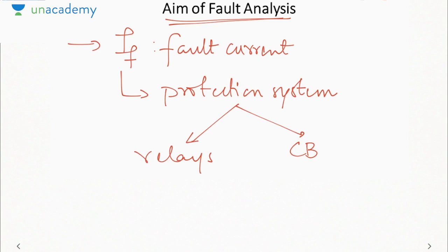That is why relay must always operate on minimum fault current. If it can sense minimum fault current, it can sense a current higher than that. Now if we talk about circuit breaker, the function of circuit breaker is to open circuit the power system for the fault condition.